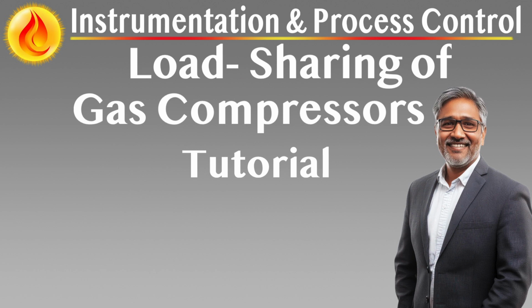Coordination with surge control: the final POC command signal, CRPOC, is calculated as CRPOC equals CRPI plus CRPOP. This command is sent to each anti-surge controller, which compares CRPOC with its own surge protection output. Whichever signal is higher, surge protection or pressure override, determines the final action. This ensures POC never undermines surge safety. If the override demand is higher, it adds extra recycle flow to stabilize pressure quickly.